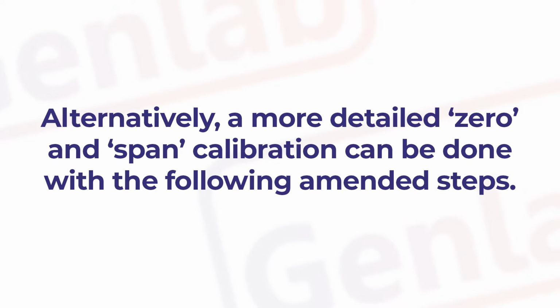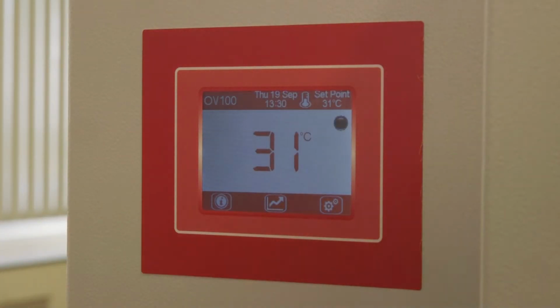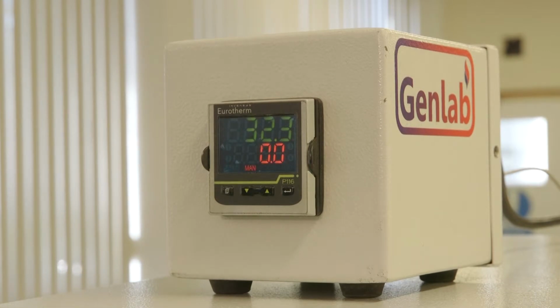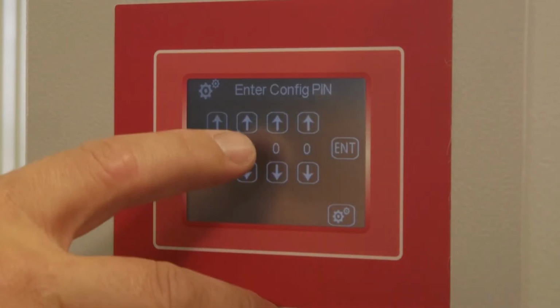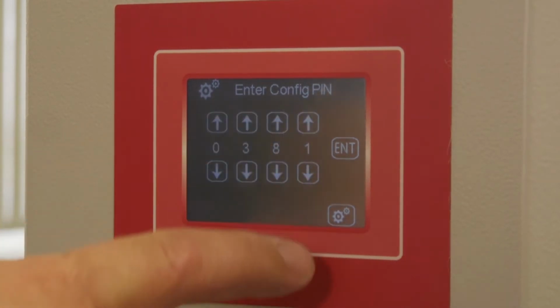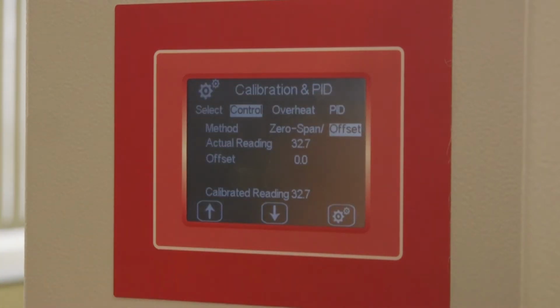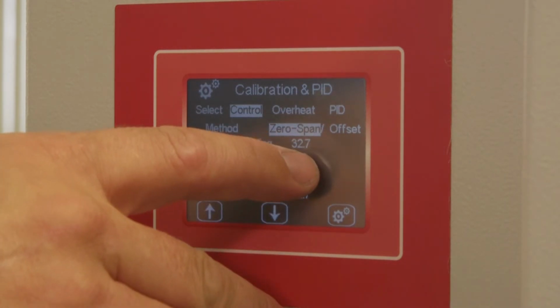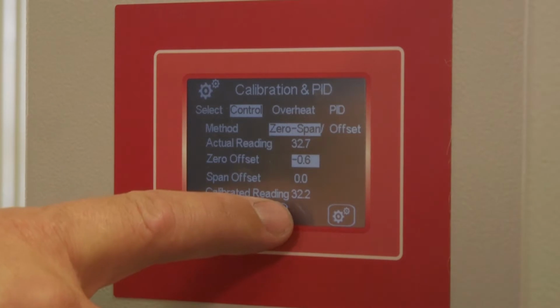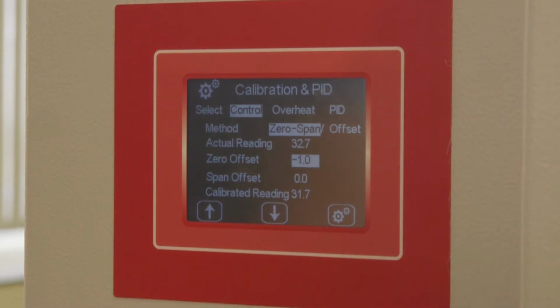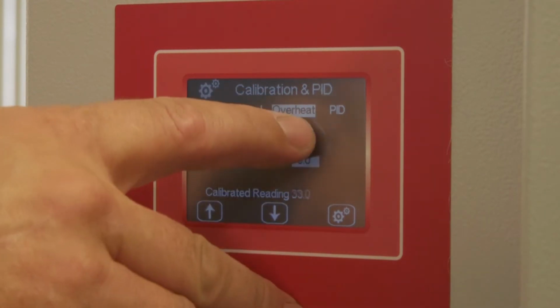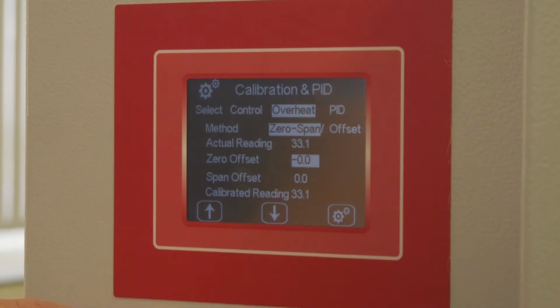Alternatively, a more detailed zero and span calibration can be done with the following amended steps. Change the set point to the lowest set point and let the oven stabilize at this temperature. Enter the password 0381 using the up and down keys and press enter. Press the calibration and PID section, then highlight the control sensor. Press the zero span feature and then highlight the zero value. Using the up and down keys, an offset is applied and the calibrated value is shown on the lower part of the screen. Repeat this procedure with the overheat sensor page.